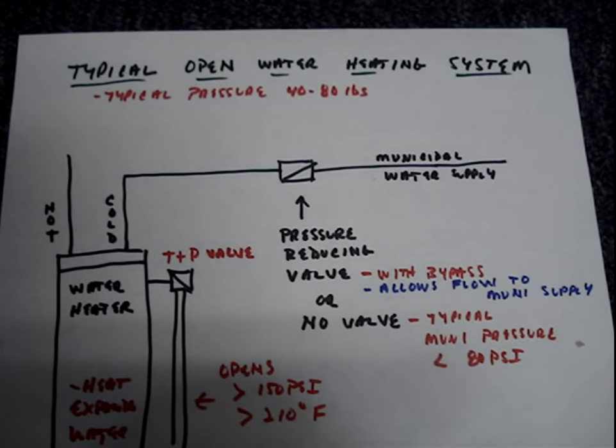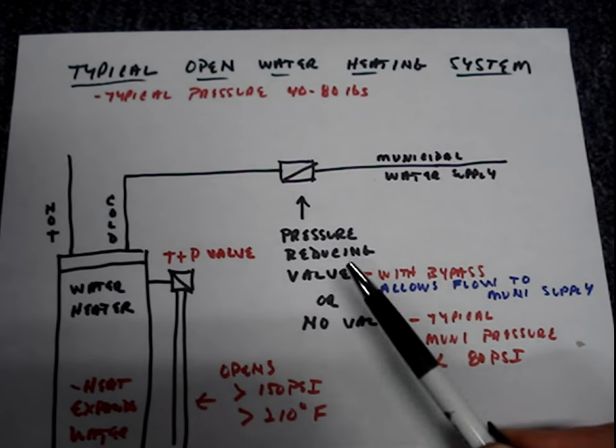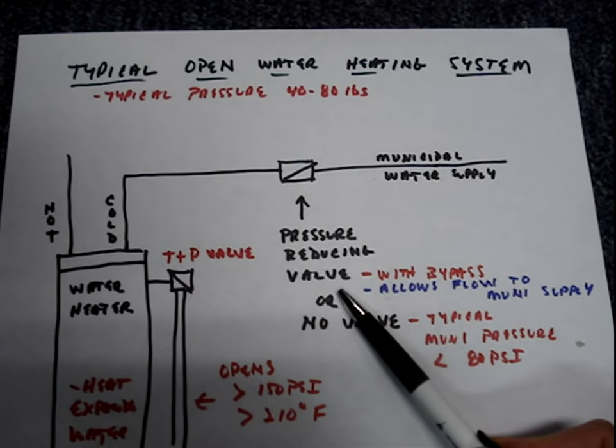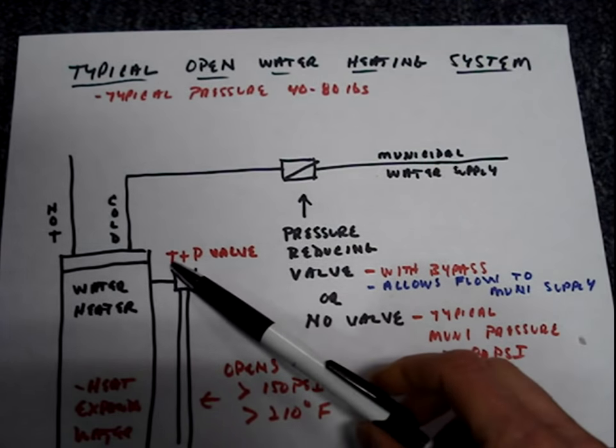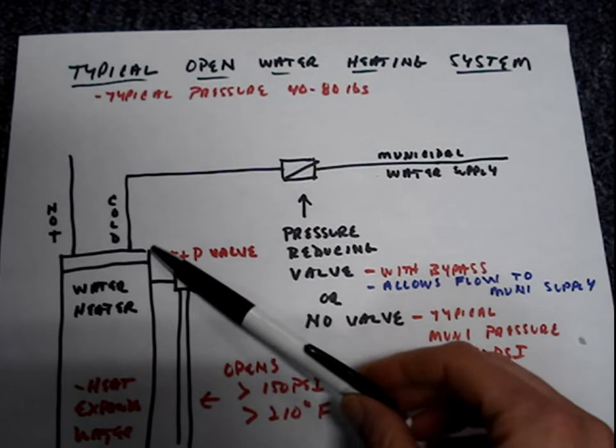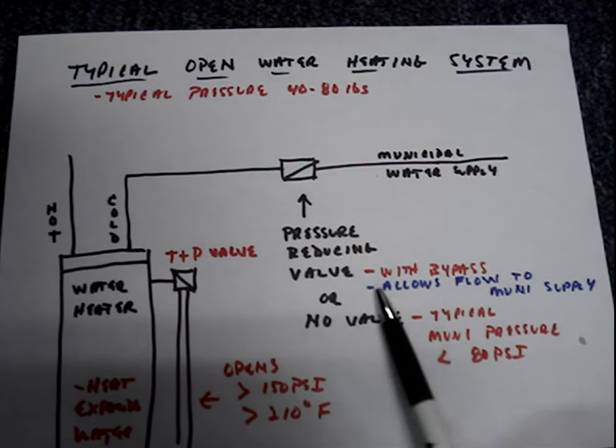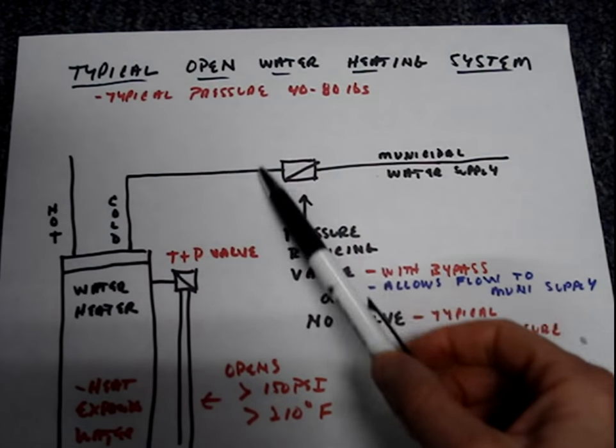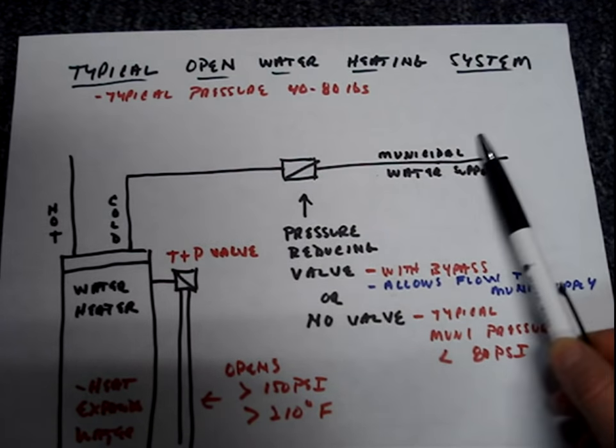An open water heating system has no valve, or it could have a pressure reducing valve with a bypass. When thermal expansion occurs on this type of system, the expanded water is able to either pass through the bypass on the pressure reducing valve, or because there's no valve, it can pass back into the municipal water supply.